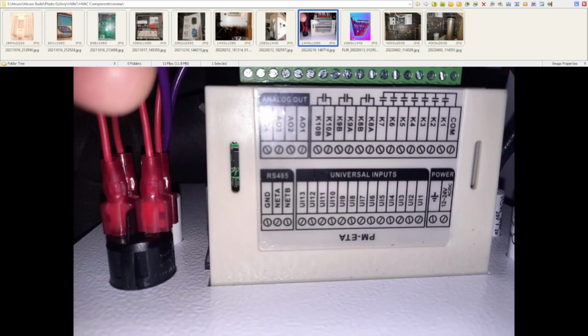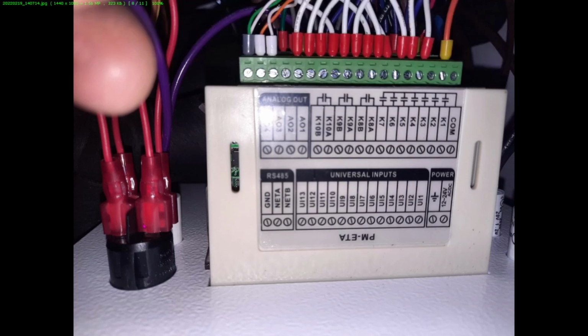On the inside of this control cabinet is the Modbus capable device, which is the PMETA. And most of the terminal strip terminations that you saw earlier are all connected to this device. And basically all of the Ks are devices that action is taken on them. So they are operating something, and all of the U's are inputs like temperature sensors and pressure sensors and the like.